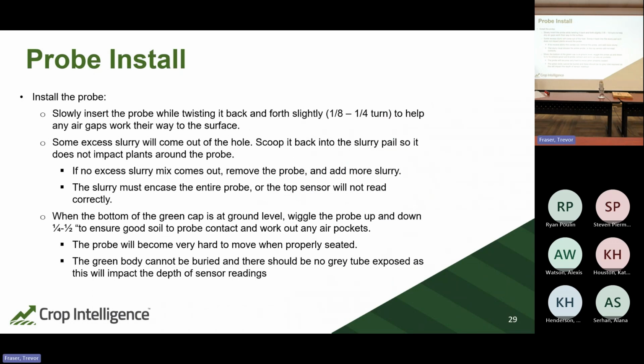So when we're installing the probe, you're going to install the probe slowly. You don't want to force it into the hole too fast, because all you're going to do is cause air pockets to get stuck underneath the probe. You're going to be twisting the probe back and forth about a quarter to an eighth of an inch turn to try and get those air pockets that are underneath there to come up and escape out around the probe, so that the slurry mix makes complete contact around it.